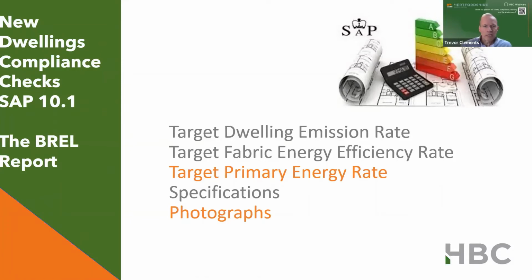So apart from that, we also need to see that the minimum base standards, i.e. the bottom line standards, have been met in the design for fabric efficiency in terms of U values of the thermal elements, and also minimum efficiency levels for the fixed building services. And this data is all going to be included in what's going to be called a BREL report, which stands for Building Regulations England Part L, apparently, as I read. And that needs to be given by the applicant to the building owner and also to building control. And they will be assisted in producing that by their energy specialist, energy assessor.